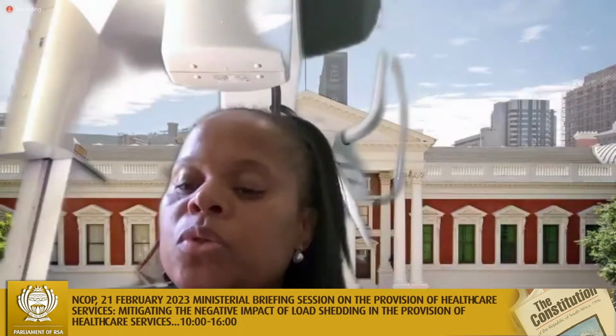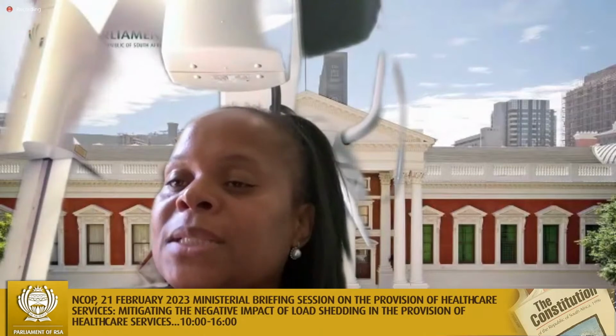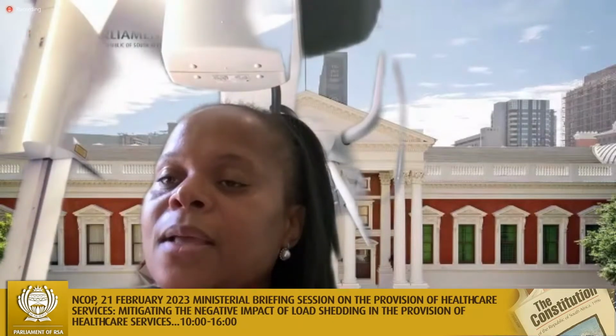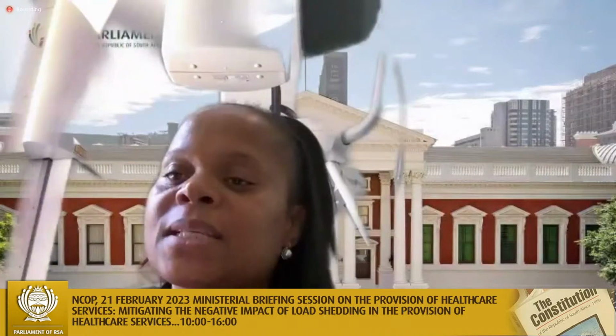So load shedding on its own has affected water supply in our hospitals and clinics. Many of our clinics, if not 90%, depend on boreholes because they are in rural areas where the community does not even have water themselves. The boreholes depend on electricity for pumping, and some of these clinics do not have generators. With load shedding we can't pump water, and these are clinics running deliveries. That's why we need more generators and alternative power supply, because it's a serious problem. Our chiller plants and air conditioners in theaters also require power, and some theater equipment needs water with pressure. So when municipalities are affected by load shedding, like in Petersburg, they can't supply us with water either.